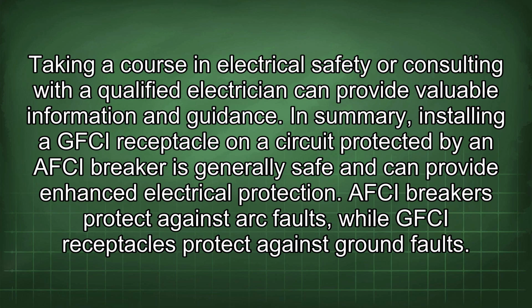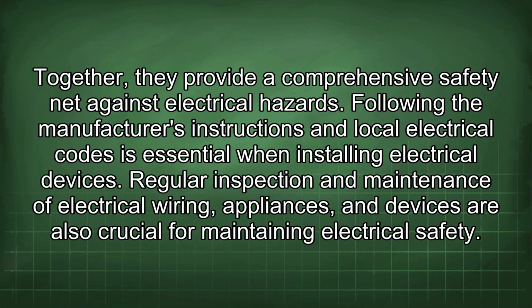In summary, installing a GFCI receptacle on a circuit protected by an AFCI breaker is generally safe and can provide enhanced electrical protection. AFCI breakers protect against arc faults, while GFCI receptacles protect against ground faults. Together, they provide a comprehensive safety net against electrical hazards.